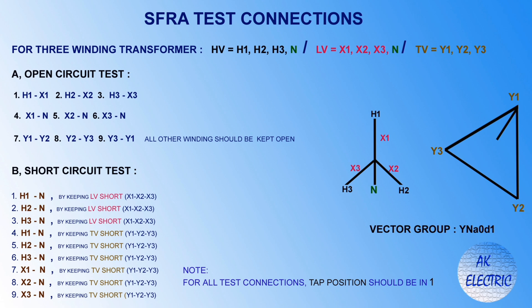For a three-winding transformer: HV and LV sides are in star connection and TV side is in delta connection, with a common neutral for HV and LV. For the open circuit tests, nine combinations are tested: H1 to X1, H2 to X2, H3 to X3, X1 to neutral, X2 to neutral, X3 to neutral, Y1 to Y2, Y2 to Y3, and Y3 to Y1 — with all other windings kept open. For short circuit tests with LV shorted: H1 to neutral, H2 to neutral, H3 to neutral. With TV shorted: H1 to neutral, H2 to neutral, H3 to neutral, X1 to neutral, X2 to neutral, X3 to neutral. Tap position should be at one for all tests.